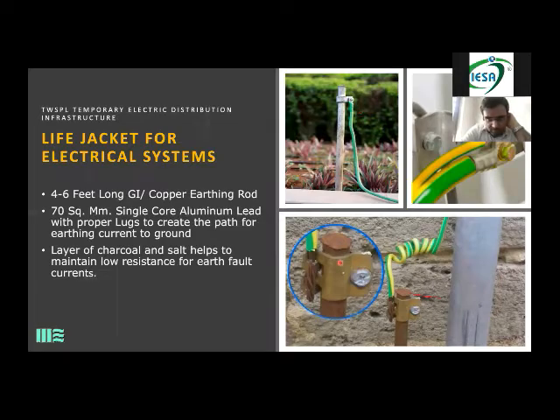So there are two types. Either you can use copper rods also. See, there are different types of earthings which can be done on site. Most commonly for live events, it is suggested that we use rods. There is pipe earthing also, there is plate earthing also, there is chemical earthing also, there is this GI rod earthing also.